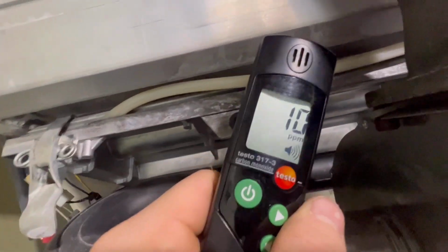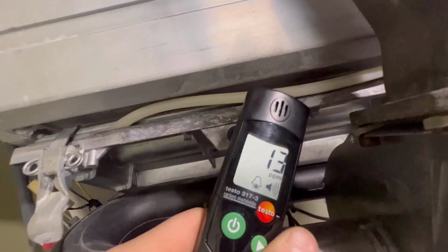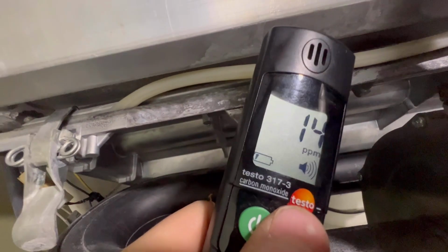Hey Chris? Yeah. You know, whoever put this motor, this draft inducer, yeah, you know, this is a carbon monoxide detector here. Yeah. And it's reading 14 parts per million, and you can feel the immense heat coming out of that.